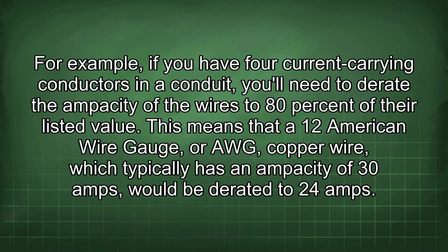For example, if you have 4 current-carrying conductors in a conduit, you'll need to derate the ampacity of the wires to 80% of their listed value. This means a 12 American Wire Gauge, or AWG, copper wire, which typically has an ampacity of 30 amps, would be derated to 24 amps.